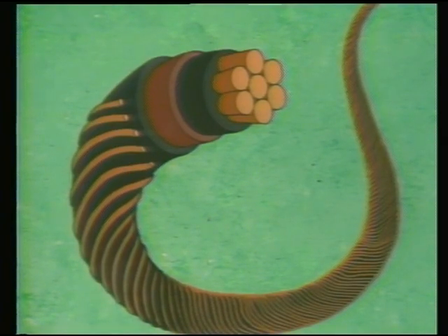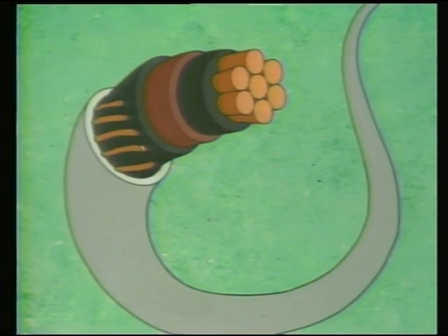The metallic shield is a conductive material, usually copper or aluminum, that can be made up of concentric wires or of metallic taped ribbon. On this cable, the final outermost layer covering the metallic shield is the cable jacket or sheath. It serves as a protective layer for the cable insulation and other shield layers, and it's usually made of a non-conductive material, such as plastic or rubber.